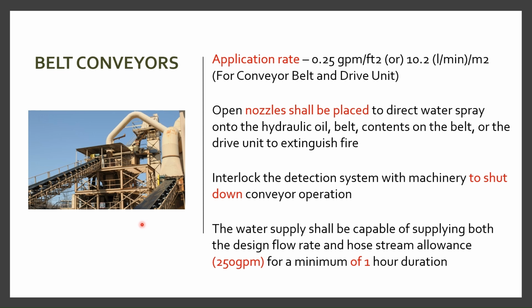So during a fire, we need to shut down the conveyor operation. Here it's mentioned to interlock the detection system with machinery to shut down conveyor operation. We have to make sure of this. And also, please note, the water supply shall be capable of supplying both the design flow rate and a hose stream allowance of 250 GPM for a minimum of 1 hour duration. This is also a major point you need to remember when you are finalizing the demand for the water spray system. We need to consider the design flow rate and add 250 GPM to it, then we will get the system demand.